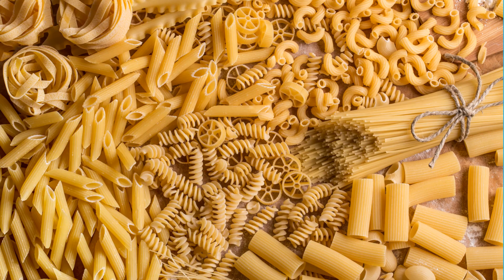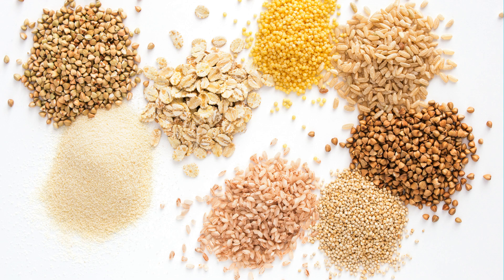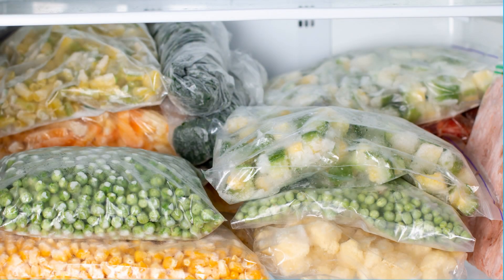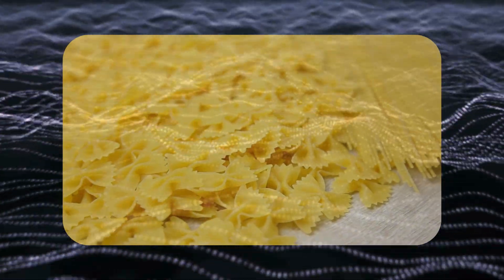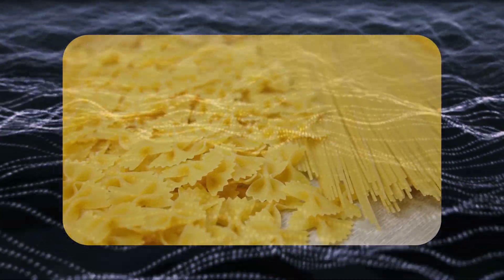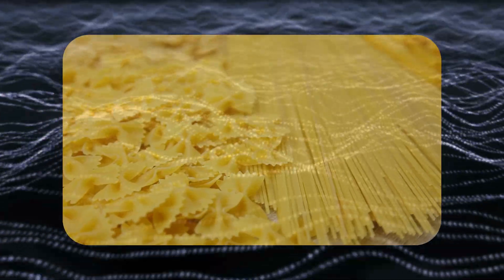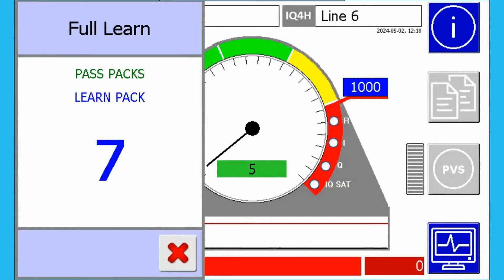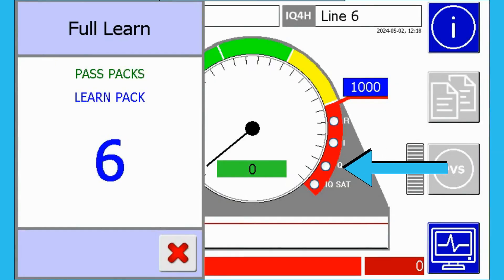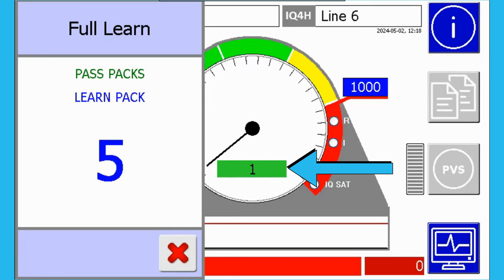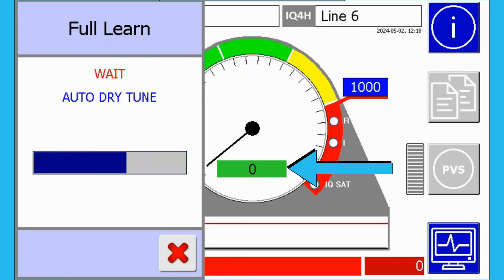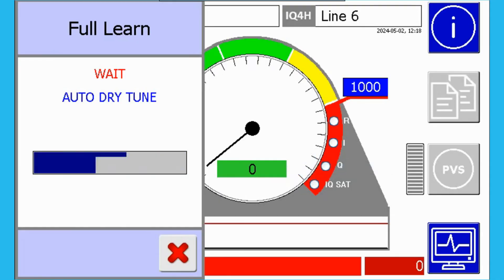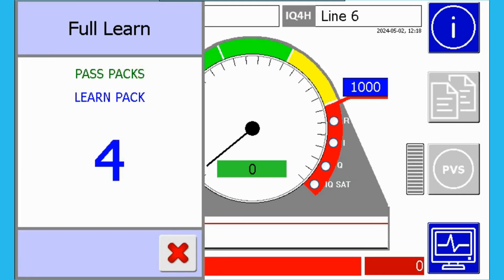Dry products, which may include foods such as dried pasta, grains and other produce that are deep frozen to the core, will not show any conductive or magnetic properties that will disturb the electromagnetic field as it passes through the head. As the metal detector tries to recognize these products without any field interference, which also results in very low signals, it will automatically switch to a dry setting that has been pre-configured. An auto-dry tune message will appear when these products are attempted to be learnt, which will signify the product is dry and is choosing the optimized setting required for these types of dry products.